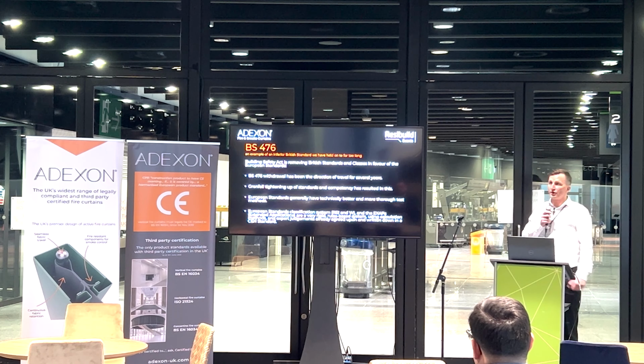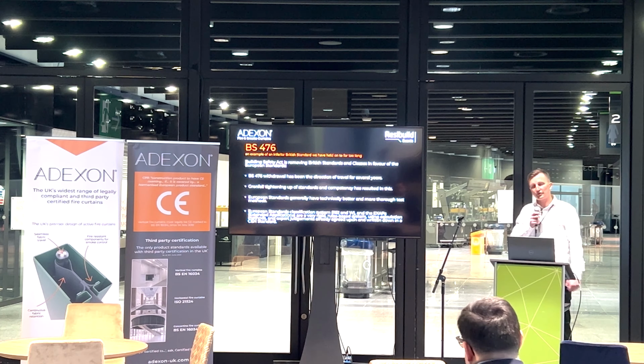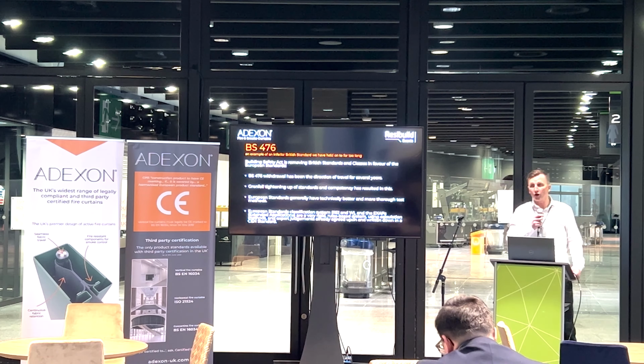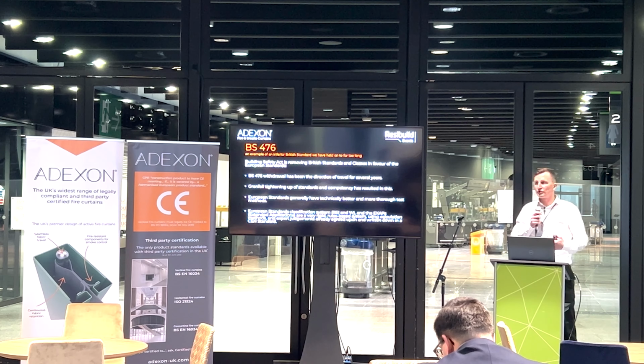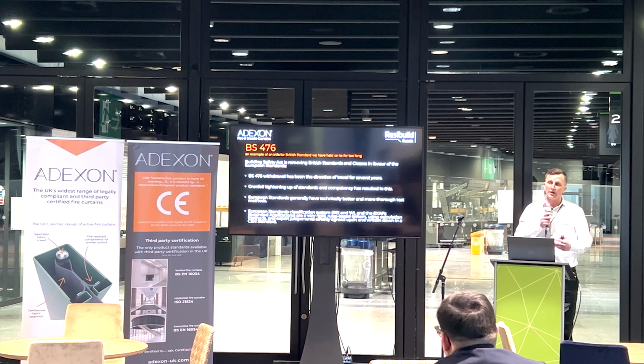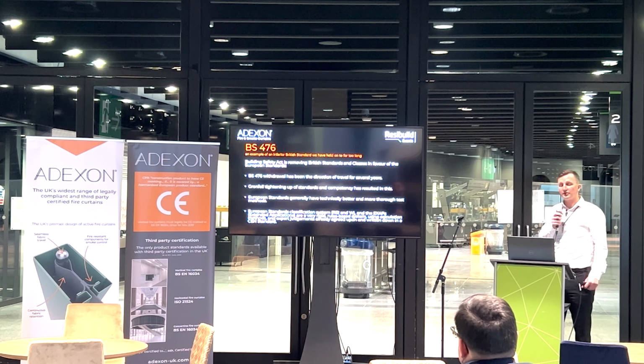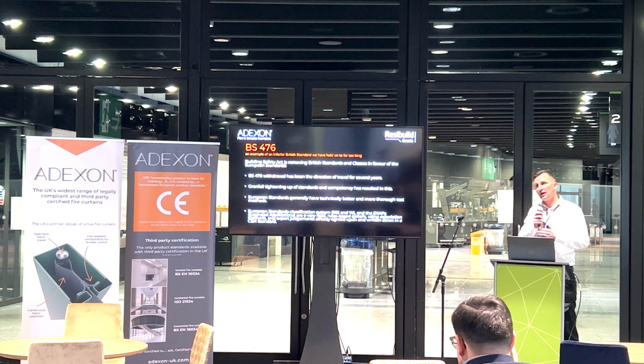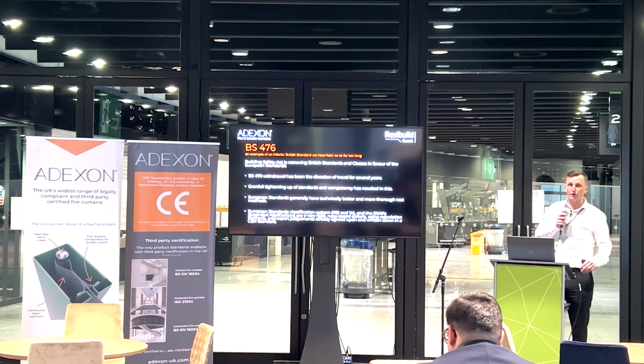And it is one of the results of Grenfell, so the tightening up on standards and competency. And what we know, we've actually known this for 20 years as a country, and it's not a great reflection on us that we've held on to BS476. So we've known since 2000 that the European fire test is a more rigorous test. Just as an example, the plate thermometer used in the European fire test, 1634 Part 1, will mean that the product tested has up to 30% greater thermal exposure.